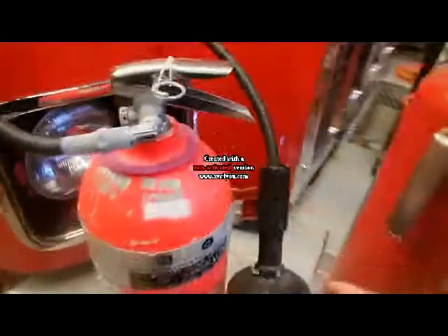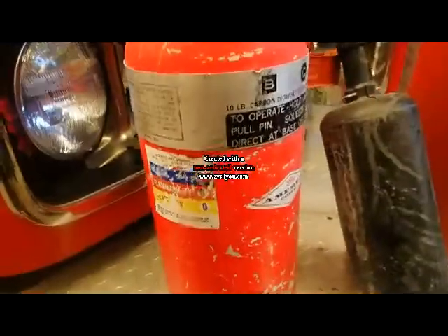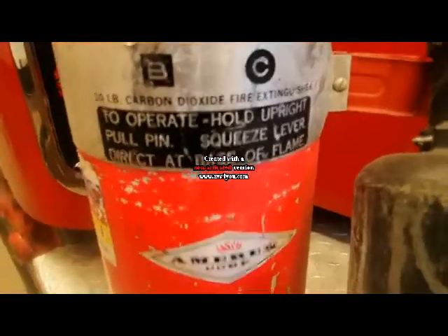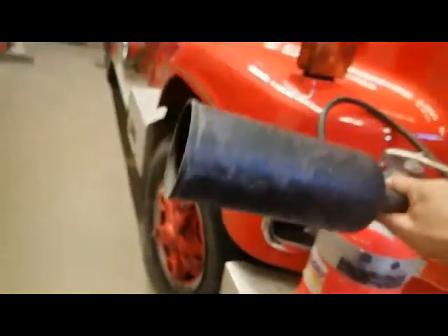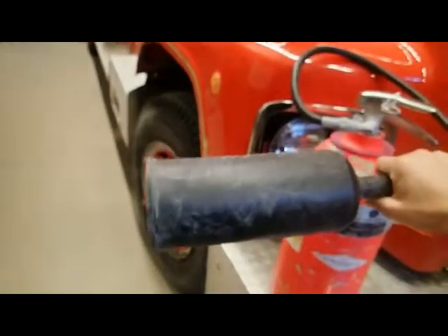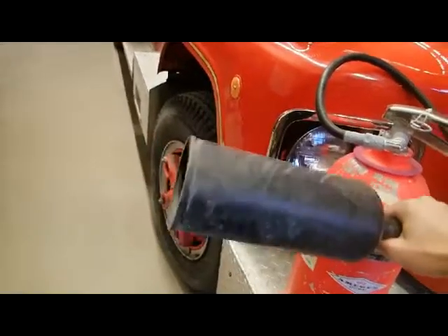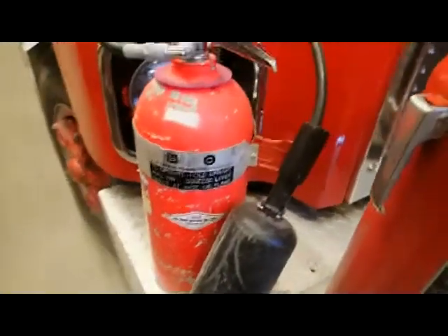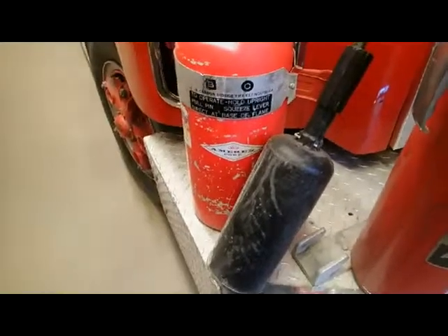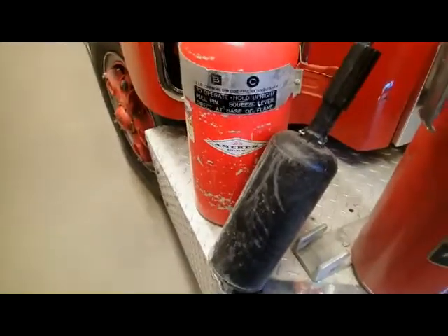And then finally we have the CO2 extinguisher. And this one is going to be approved for Class B and Class C fires. You can easily identify this one because it has the cone. As the CO2 comes out, it's going to be cold and super frosty. Then the cone just protects your hand from that cold air as it comes out. And what that's going to do is it's going to cool the environment, and the main thing it does is it displaces the oxygen around the fire and makes it unable to burn.